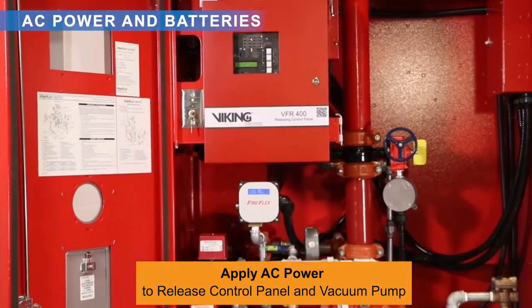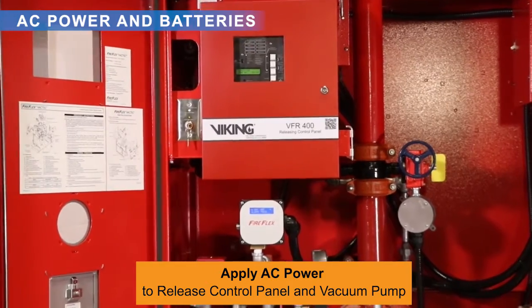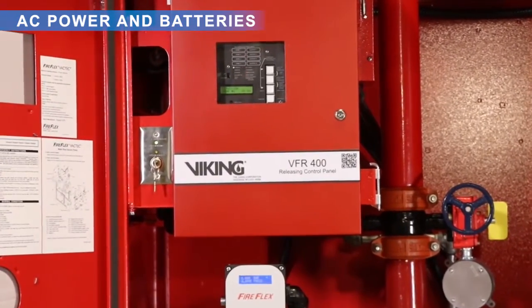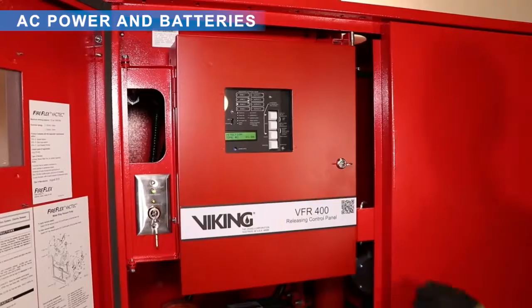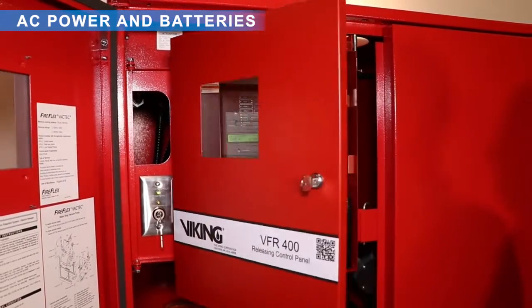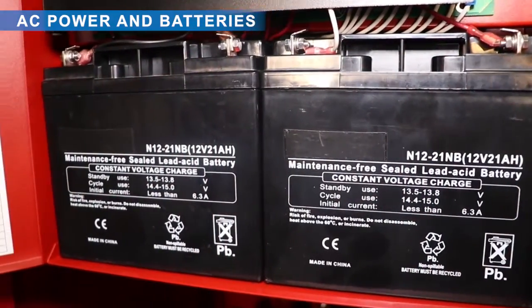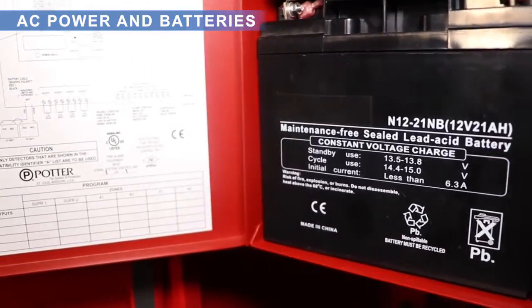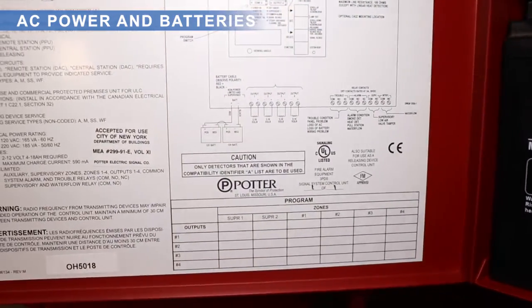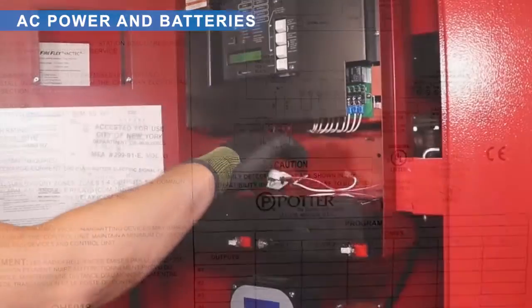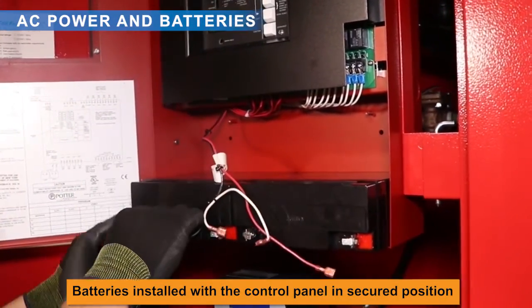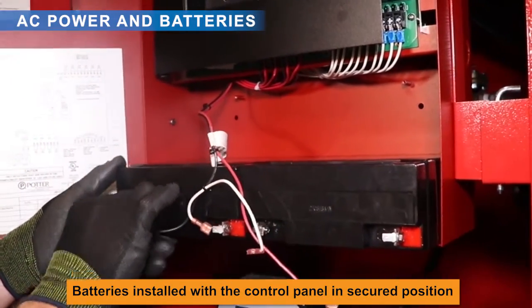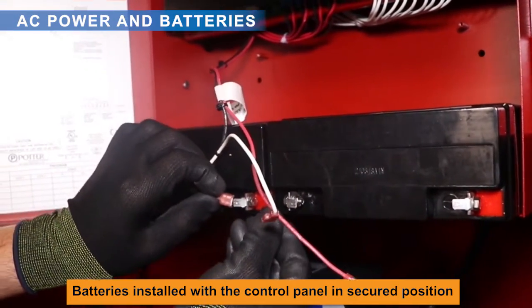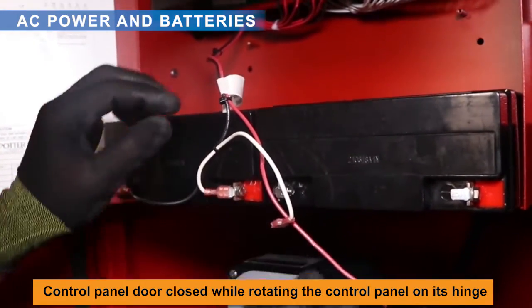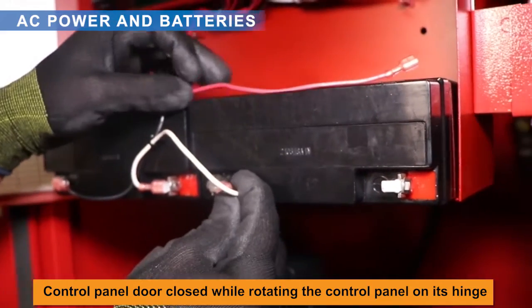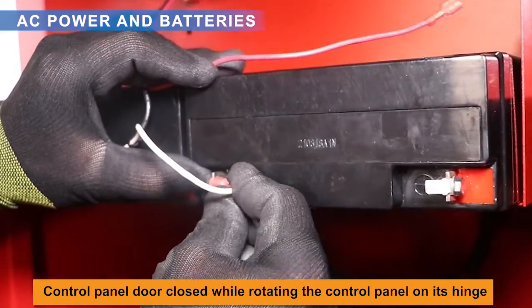Apply AC power to the release control panel and to the vacuum pump. Install and connect the batteries. Verify proper battery capacity and polarity. Batteries shall be installed with the control panel in secured position. Control panel door should always be closed while rotating the control panel on its hinge.